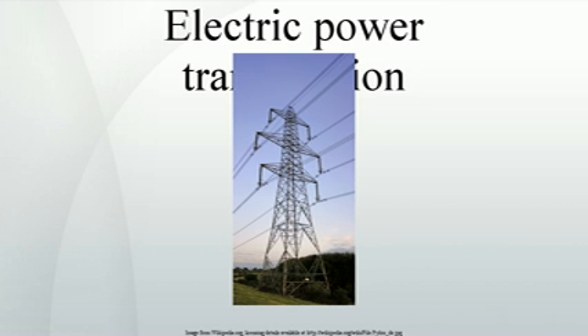Capacity. The amount of power that can be sent over a transmission line is limited. The origins of the limits vary depending on the length of the line. For a short line, the heating of conductors due to line losses sets a thermal limit. If too much current is drawn, conductors may sag too close to the ground, or conductors and equipment may be damaged by overheating. For intermediate length lines on the order of 100 kilometers, 62 miles, the limit is set by the voltage drop in the line.